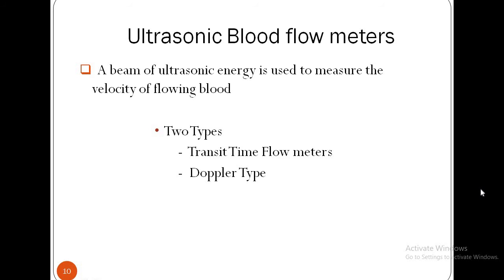There are basically two types of ultrasonic blood flow velocity meter. The first type is a transit time velocity meter and the second is the Doppler shift. For routine clinical measurements, the Doppler instrument has been used.